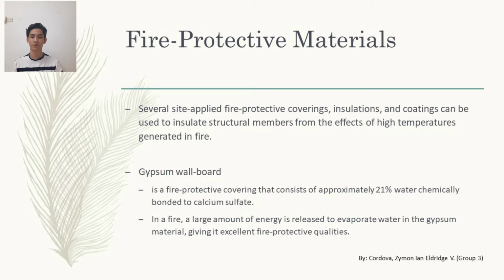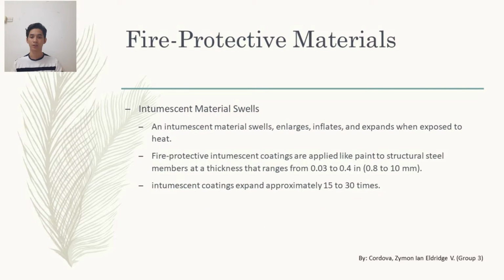Fire protective materials. Several site-applied fire protective coverings, insulations, and coatings can be used to insulate structural members from the effects of high temperatures generated in a fire. An example of this is gypsum wallboard. It's a fire protective covering that consists of approximately 21% water chemically bonded to calcium sulfate. In a fire, a large amount of energy is released to evaporate the water in the gypsum material, giving it excellent fire protective qualities. Another one is intumescent materials.